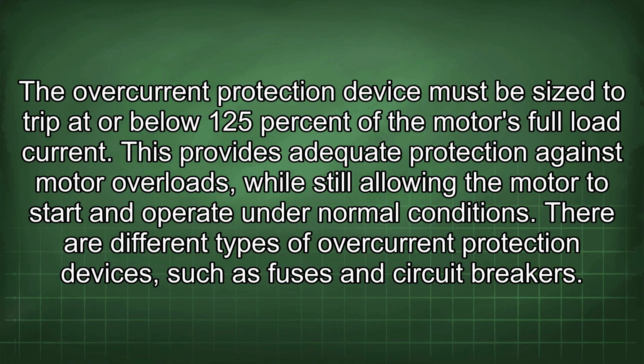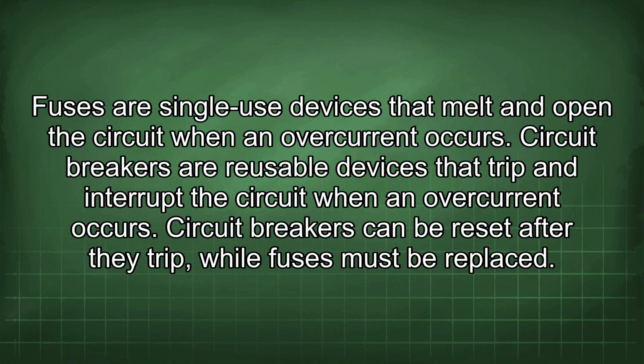There are different types of overcurrent protection devices, such as fuses and circuit breakers. Fuses are single-use devices that melt and open the circuit when an overcurrent occurs. Circuit breakers are reusable devices that trip and interrupt the circuit when an overcurrent occurs. Circuit breakers can be reset after they trip, while fuses must be replaced.